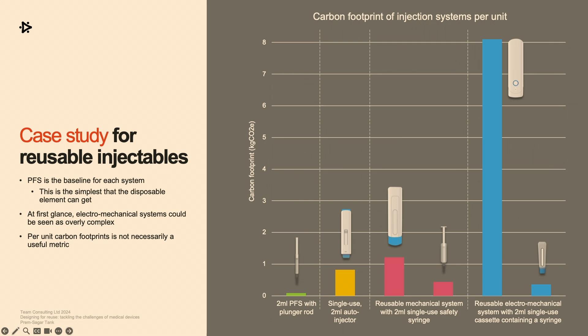So we'll now look at through life. So we've extrapolated this into a cumulative graph looking at 120 uses. And just to explain how it works, your initial peak here, an initial jump up, if you like, is based on your first disposable and your reusable device. And the gradient subsequent to that is the disposable only. So as you can see, the electromechanical system, as you may have expected, does not perform well after a single use, whereas almost all of the other ones perform pretty well.